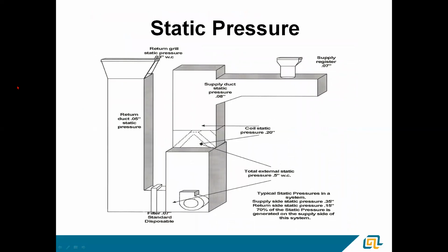Where do we measure static pressure? We would measure it between the filter and the blower for a return static, which would be a negative number. And then we measure it after the heat exchanger, but before the coil. And that, of course, would be a positive number where we're blowing. Those two numbers added together, forget the plus and minus, they really don't factor into this, is what your total external static pressure is. And that's what the blower's working against. That's where the blower performance charts are set up. That's where you have a good ballpark of what you're moving, how much you should be moving.